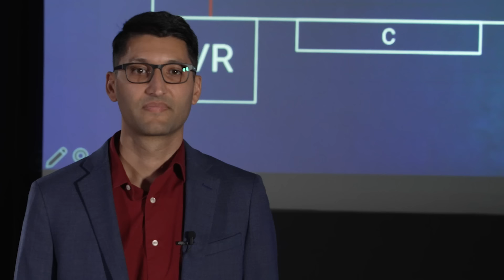Another trend to address the current density, efficiency, and performance challenges is simply to move the location of the VR. Most approaches today take a lateral power delivery approach, with the VRs on the top or bottom side of the board. Power flows laterally along the layers of the PCB, and because the distance from the VR to the chip can be significant, it leads to a lot of additional power loss and other power delivery network challenges. So a new alternative is to place the VR on the bottom side of the circuit board directly beneath the AI processor chip.